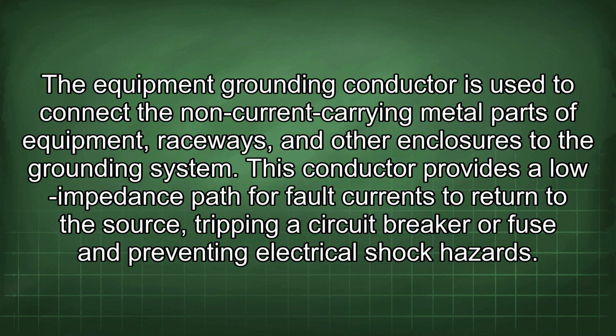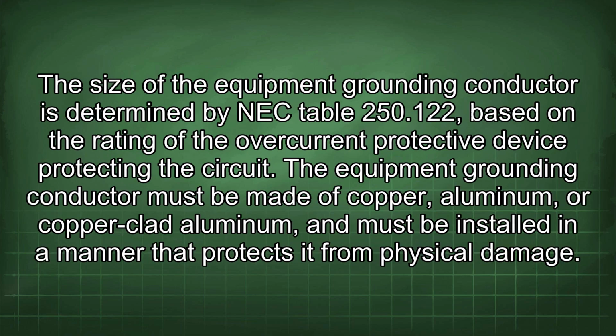The equipment grounding conductor is used to connect the non-current carrying metal parts of equipment, raceways, and other enclosures to the grounding system. This conductor provides a low impedance path for fault currents to return to the source, tripping a circuit breaker or fuse and preventing electrical shock hazards. The size of the equipment grounding conductor is determined by NEC Table 250.122, based on the rating of the overcurrent protective device protecting the circuit. The equipment grounding conductor must be made of copper, aluminum, or copper-clad aluminum, and must be installed in a manner that protects it from physical damage.